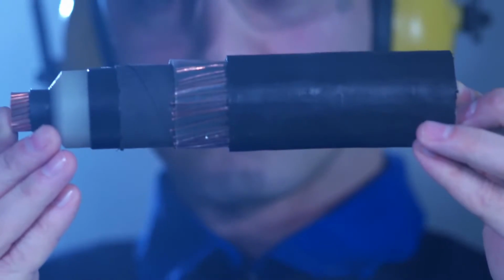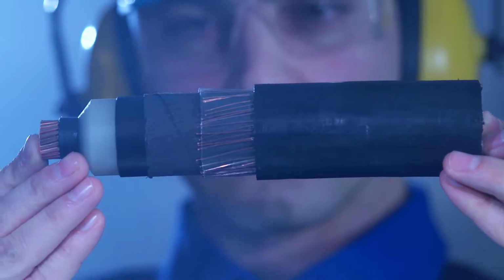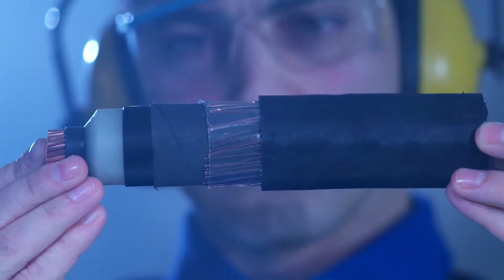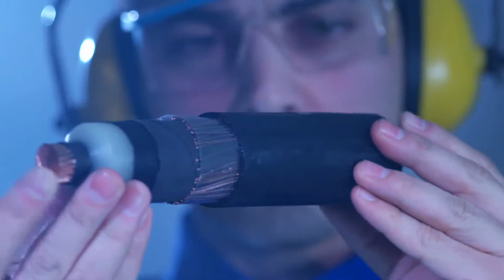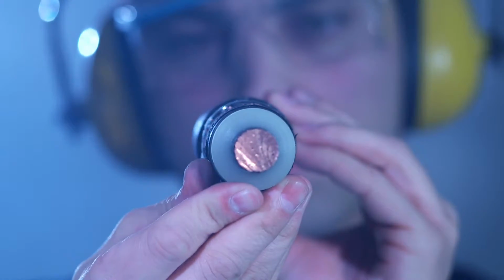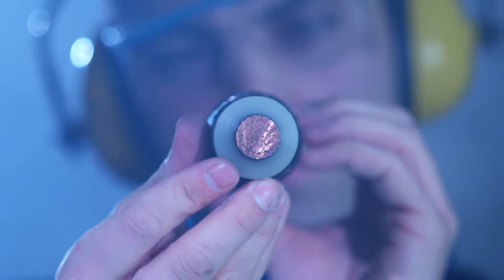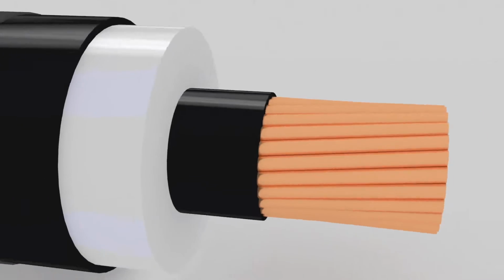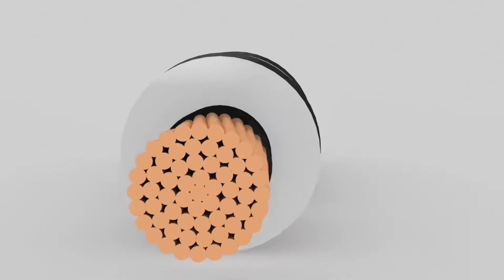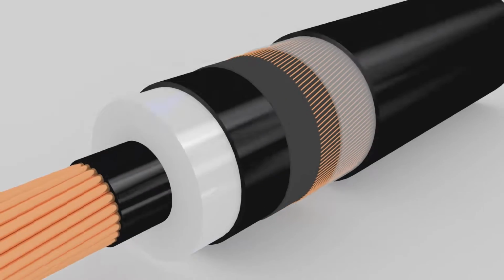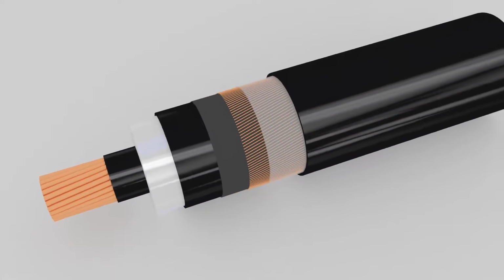This is a medium voltage cable of 35 kV. We note for comparison that this cable can provide electricity to an average settlement. Its insulating layer is made of cross-linked polyethylene. Cross-linked polyethylene cables made of a thermoset material have a number of advantages. The operating temperature of the cable is 90 degrees centigrade, while the short circuit temperature is 250 centigrade.